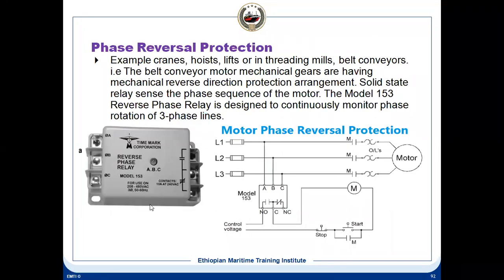How it works: you see the relay looks like this, phase reversal protection. It is basically a static relay. It has three-phase connections here, you can see A, B, C. Whenever the phase gets changed, it will trip. You see here, this has a normally open contact. If the three-phase rotation is in the proper clockwise direction, only then will this normally open contact get energized and the circuit complete for the main contactor. If phase reversal takes place, this NO contact will open, so this circuit will not complete.